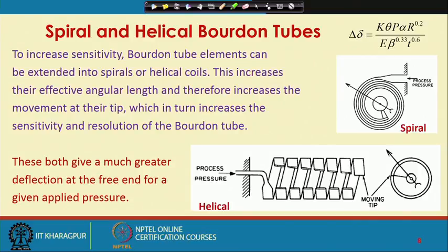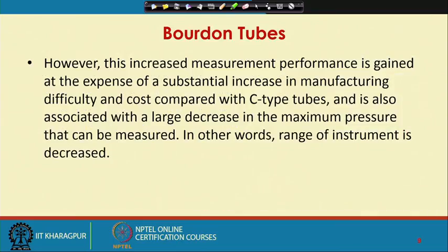Both the spiral type Bourdon tubes and the helical coils give a much greater deflection at the free end for a given applied pressure. So, both increase sensitivity. However, this increased measurement performance is gained at the expense of a substantial increase in manufacturing difficulty and cost compared with C type tubes, and is also associated with a large decrease in the maximum pressure that can be measured. In other words, the range of the instrument is decreased.